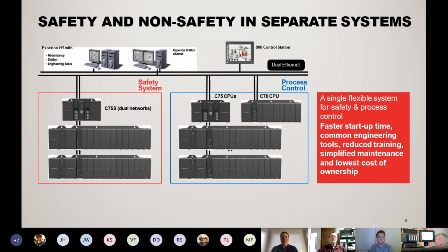So as I said, you can separate out the systems. You can have a safety system and then a process control system. You can separate them this way. In this scenario right here, both of the systems are communicating up to the same Ethernet link, which is tied into a DCS system like an Experion Honeywell system, or as well a dedicated operator interface that we're going to go through in a little bit, that has a lot of pre-built displays that you can communicate to the HC900 and interact with the process.